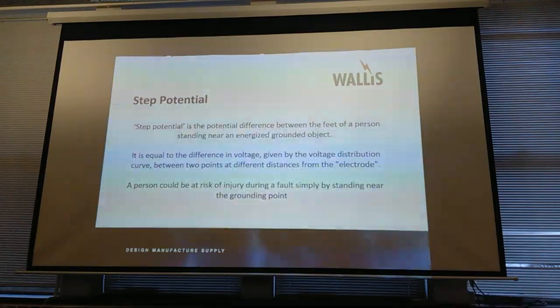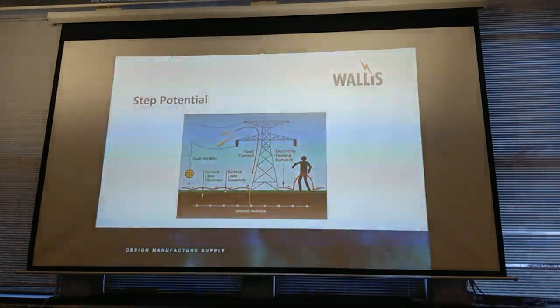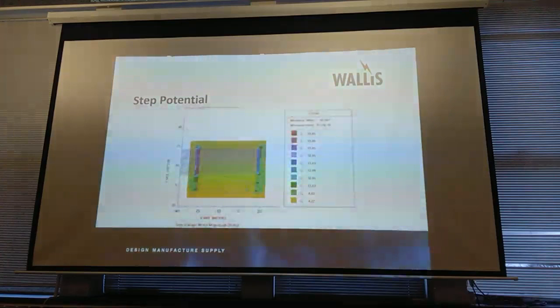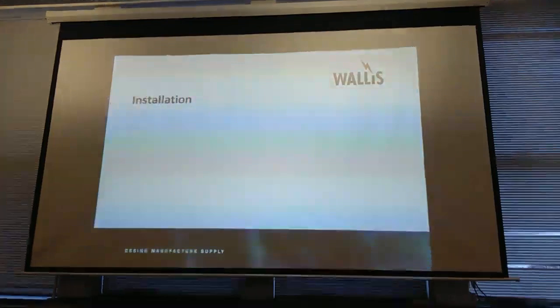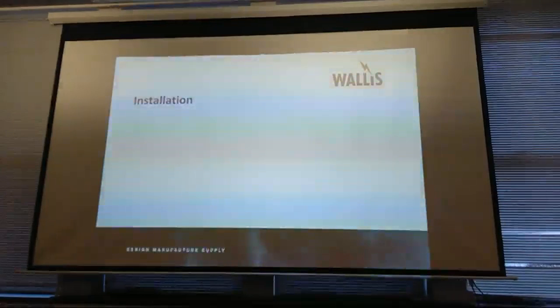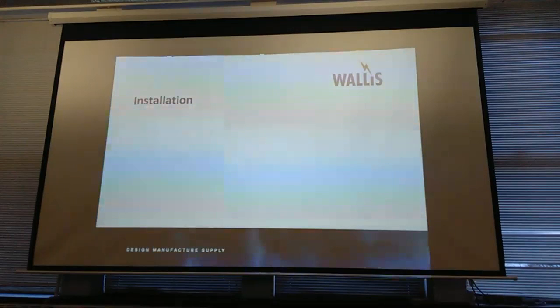So again, it's something you have to be very careful with. It's not cross his legs, up one leg, down the other. Luckily, it doesn't particularly go across the heart, but step potentials, again, that's it. The logic being, if you get the touch potentials right, the step potentials are usually right as well, because the permissibles for step are 7,000 volts, 8,000 volts for 1 second clearance time. So it's really quite high, as opposed to touch potentials, which can be a few hundred volts.